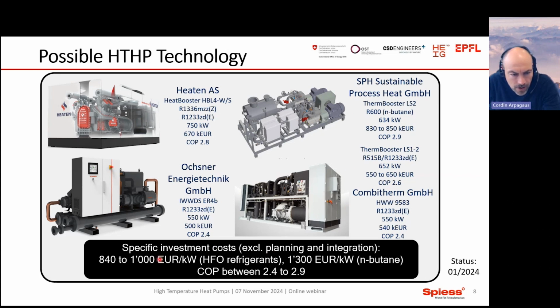And so on average, the specific investment costs for this equipment would be between 840 and 1,000 euros per kilowatt for the HFO refrigerant solutions and 1,300 euros per kilowatt for the butane heat pump. The COPs are between 2.4 and 2.9. So this was the status early this year.